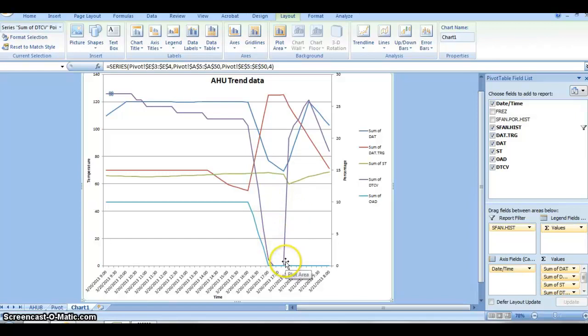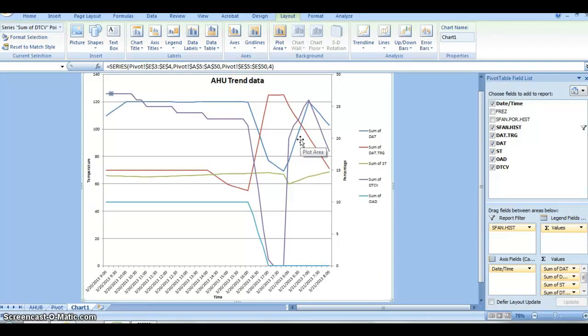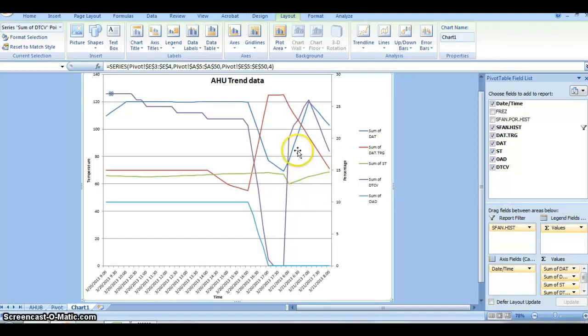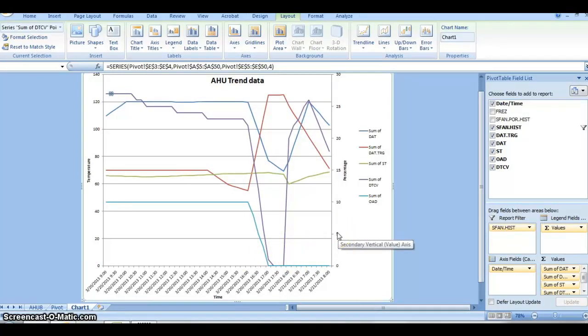The system tends to kick back on around 5:30, 6 o'clock in the morning, and it kicks on to keep that temperature up for its occupants again. You can see the outside air damper doesn't kick on probably until around 8 or 9 o'clock in the morning. That's when kids have to enter the building.